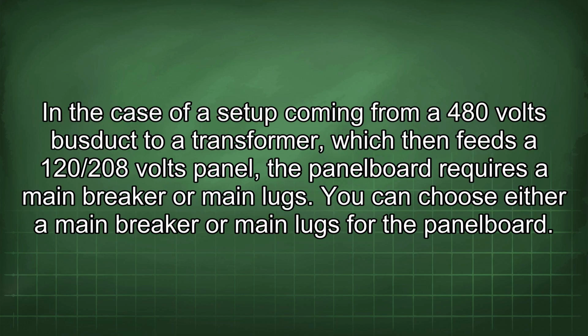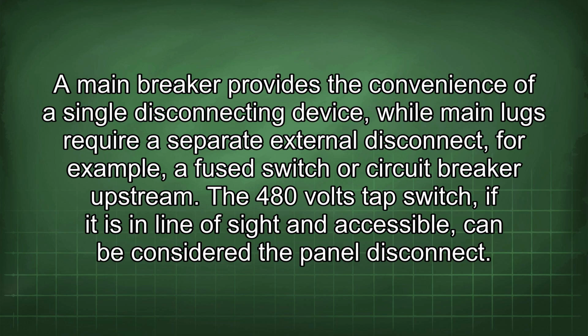In the case of a setup coming from a 480 volts bus duct transformer, which then feeds a 120/208 volts panel, the panel board requires a main breaker or main lugs. You can choose either a main breaker or main lugs for the panel board. A main breaker provides the convenience of a single disconnecting device, while main lugs require a separate external disconnect, for example, a fuse switch or circuit breaker upstream.